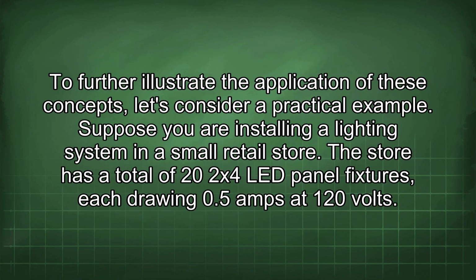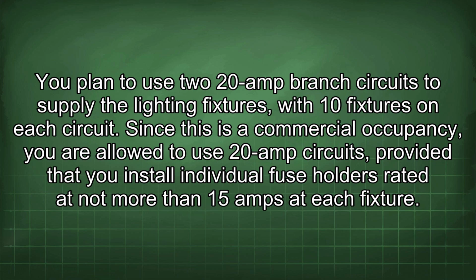To further illustrate the application of these concepts, let's consider a practical example. Suppose you are installing a lighting system in a small retail store. The store has a total of 20 LED panel fixtures, each drawing 0.5 amps at 120 volts. You plan to use two 20 amp branch circuits to supply the lighting fixtures, with 10 fixtures on each circuit. Since this is a commercial occupancy, you are allowed to use 20 amp circuits, provided that you install individual fuse holders rated at not more than 15 amps at each fixture.